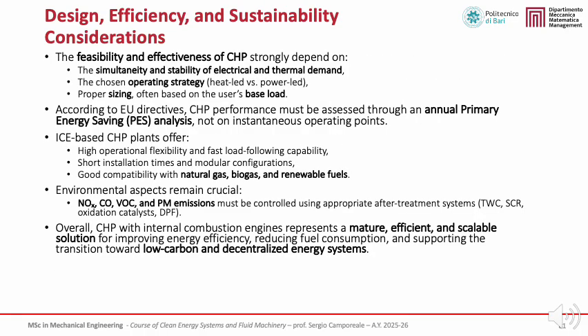From a design and operational perspective, the effectiveness of CHP systems strongly depends on matching the plant to the user's energy demand. In particular, the simultaneity of thermal and electrical loads and the choice between heat-led or power-led operation play a crucial role in determining overall efficiency and primary energy savings. According to European regulations, the performance of a cogeneration system must be evaluated on an annual basis using the primary energy saving index, rather than considering isolated operating conditions.